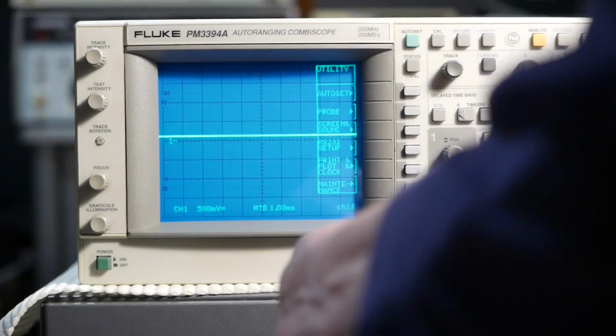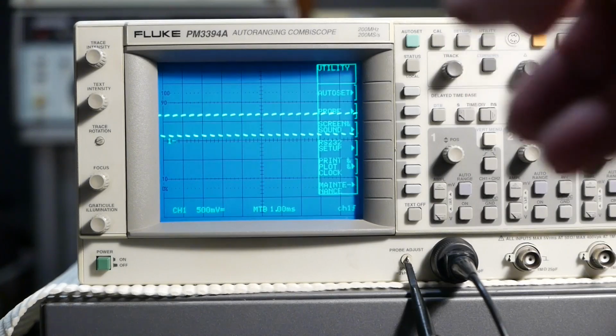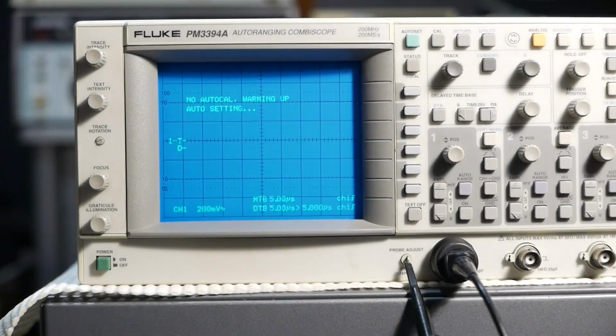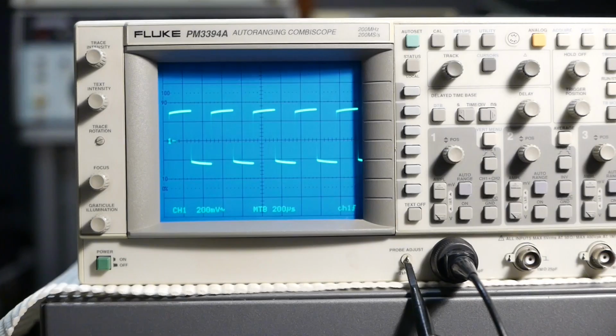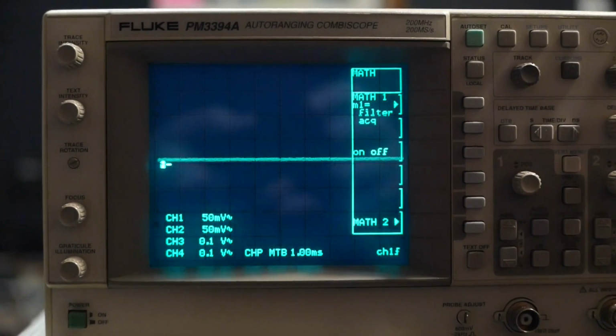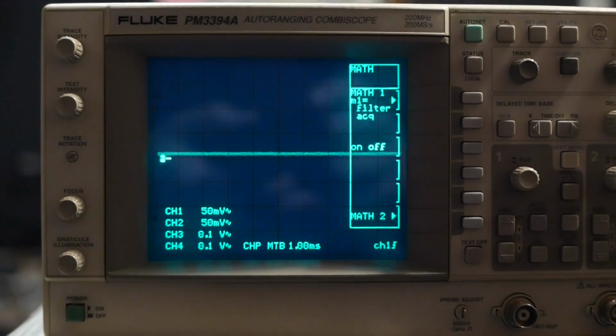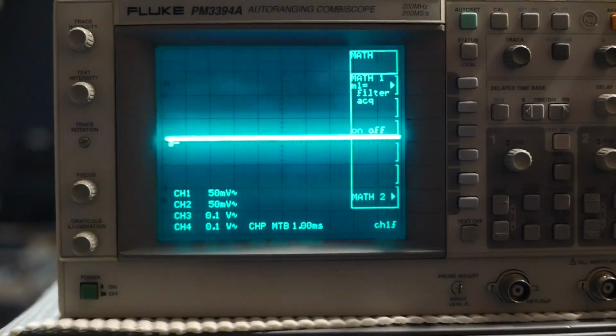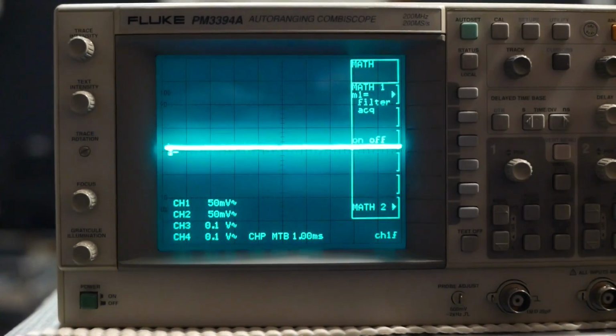I don't know why it's doing that, but it's possibly because there's a component on the verge of failure. I want to find out what's causing that fault, because if a component is about to fail, there's a reasonably good chance it could take other components out with it. So I'm going to start with visual inspection to see if there's anything cooked, hot, or burnt, and then I'll look at the power supply, because the symptom I'm seeing could possibly be caused by one of the outputs glitching. I'll start by testing the power supply, and based on the results, decide what to do next.